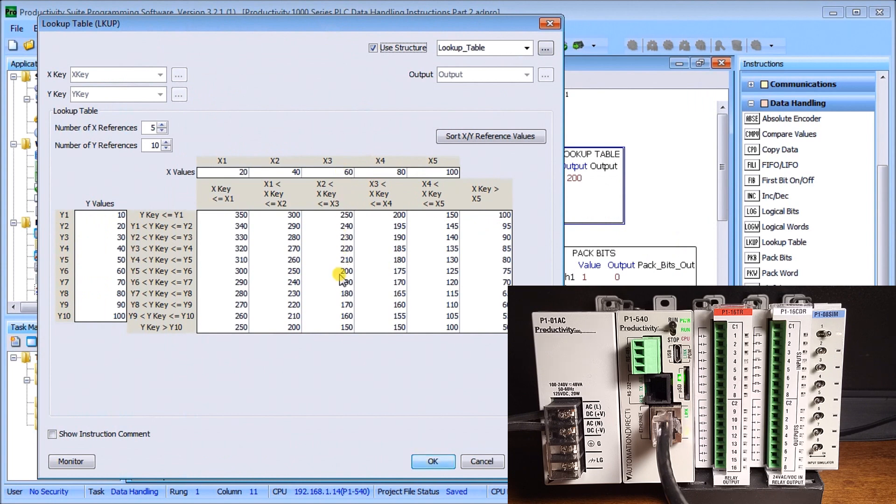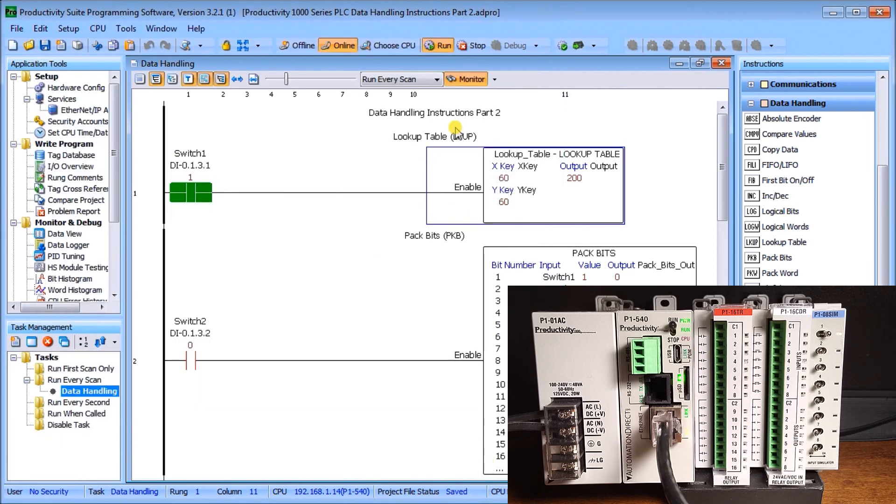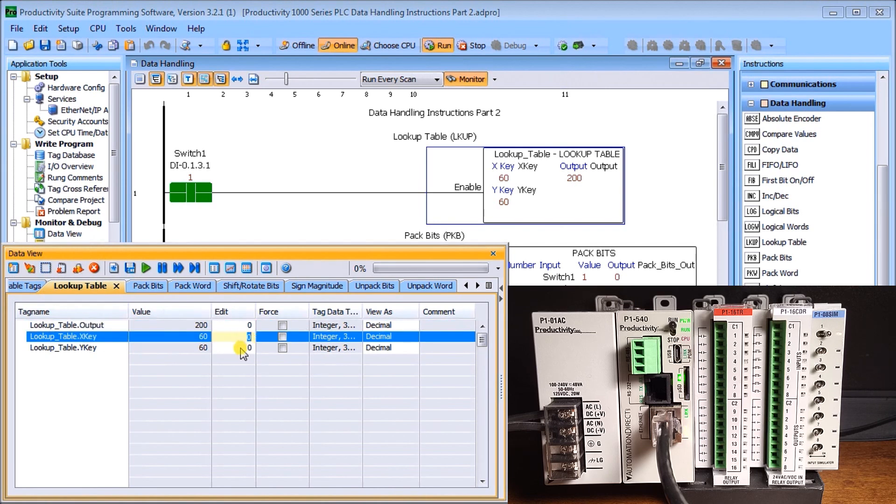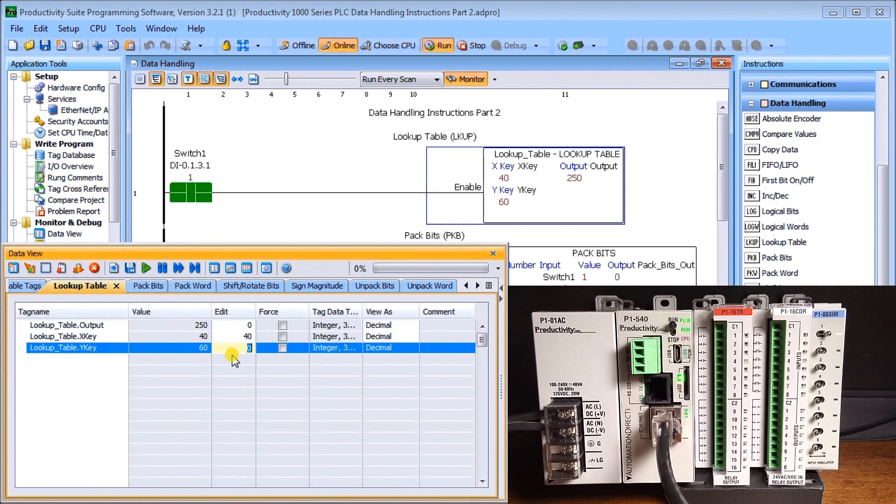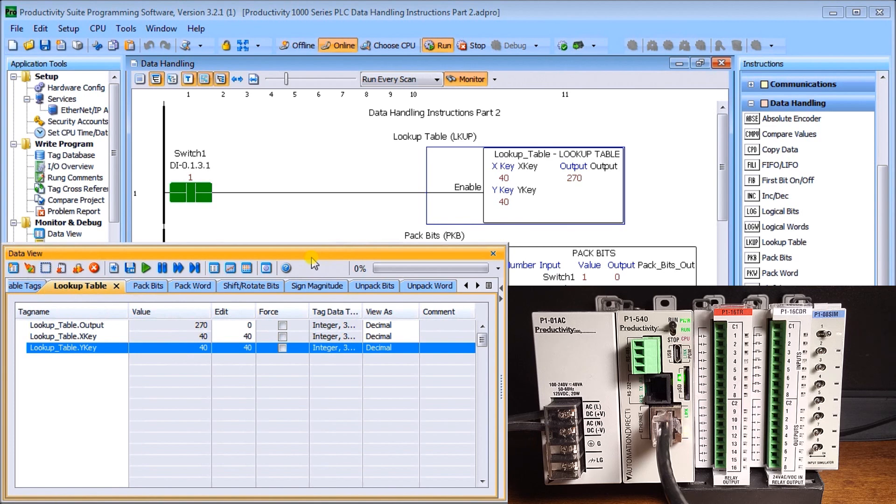Now let's change it. Let's go to x2 at 40 and 40, and we should get 270 as the output. Let's look at our data view and change the x and y. We'll put this as 40 and write that into the PLC. That automatically changes my output to 250 now. Write that in, and again we get the 270 just as expected. That's a lookup table, very good for looking at curves of motors for special functions.